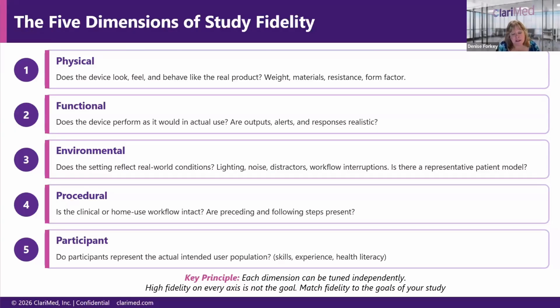What is the use environment that it's going to be used in? Because getting a COVID test in a car is different than getting a COVID test in a clinical office. And so those are things that need to be considered as you're thinking about usability, as you're thinking about risks, as you're thinking about how you're going to evaluate your product in formative studies to improve your user interface, and ultimately how you're going to evaluate it in summative. And so those are kind of key foundational building blocks for a usability program, and they matter. And there's a reason why we set those at the beginning of a project and refine them along the way as we learn things.